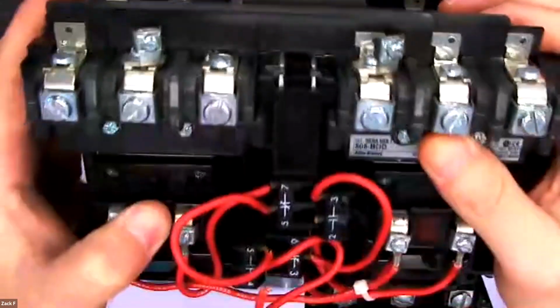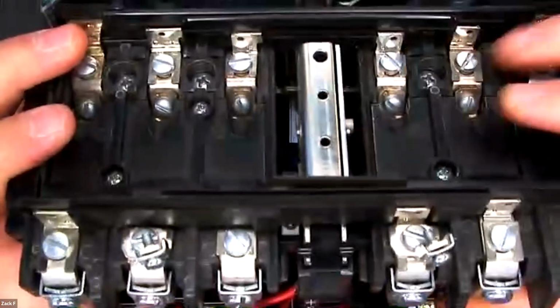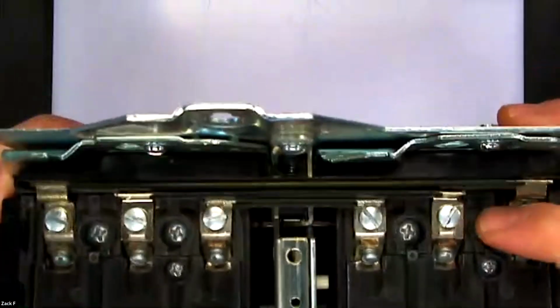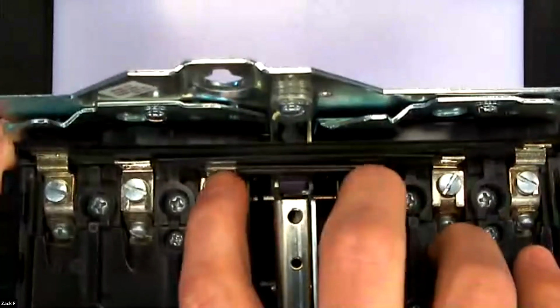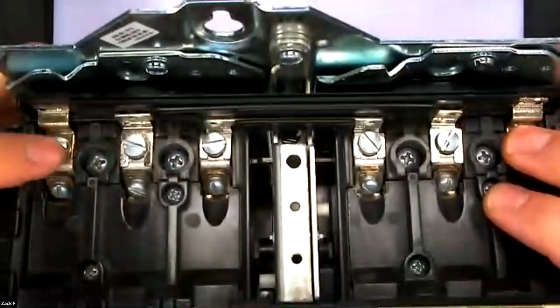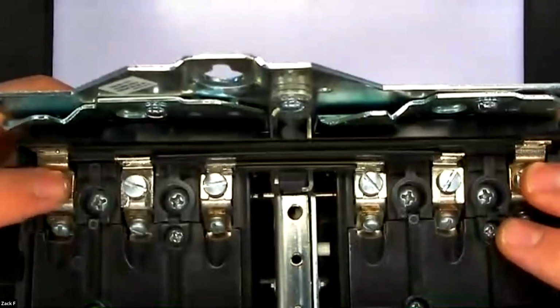So you can see on these lugs, all I'm doing is flipping this up so you can see the top. The lugs are up front, but the part that connects the 2 starters together is back here. What happens here is this phase A is connected to phase C over here. B stays the same, and then phase C over here is connected to phase A on this side. So it's switching 2 of the leads, A phase and C phase.